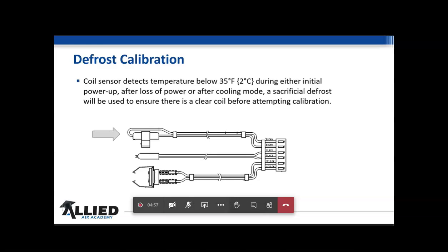So defrost calibration. The coil sensor detects temperatures below 35 degrees, 2 degrees Celsius, during either an initial power up or after a loss of power or after cooling mode. A sacrificial defrost will be used to ensure that there is a clear coil before attempting calibration. Let me kind of walk us through that. If you cut the power off and back on, it's going to have to recalibrate itself, the initial calibration, okay? If you lose power, same thing. If you have yours set like mine, and I mentioned the weather for a reason, this morning my heat was on, this afternoon my AC will come on. Well, back tonight when it goes back in, because it went in the cooling mode, it will have to calibrate again. But this is not the only time it is calibrating.